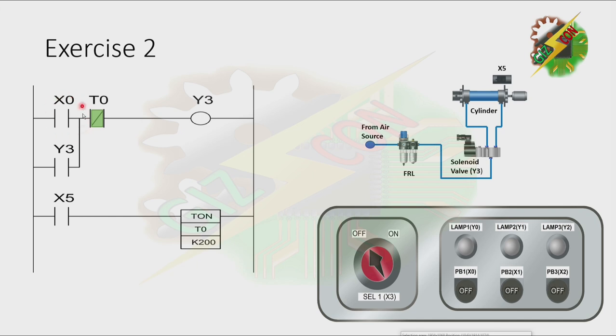Now let's analyze my program. If we press X0 or PB1, Y3 will turn on, and Y3 will not turn off because there is a latching here, even if we release X0. The only way to turn it off is by activating T0. To activate T0, we need to energize X5, which is the fully extended position.